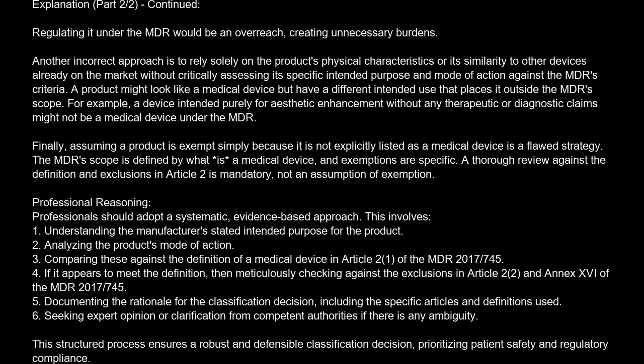For example, a device intended purely for aesthetic enhancement without any therapeutic or diagnostic claims might not be a medical device under the MDR. Finally, assuming a product is exempt simply because it is not explicitly listed as a medical device is a flawed strategy. The MDR scope is defined by what is a medical device, and exemptions are specific. A thorough review against the definition and exclusions in Article 2 is mandatory, not an assumption of exemption.